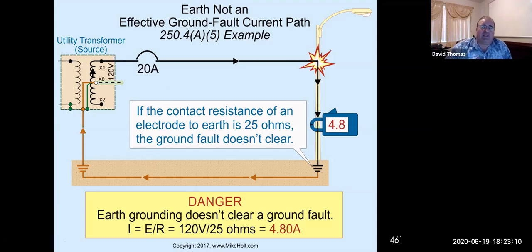And actually, this is the situation where that little girl got, well, not exactly like this one, but because the neutral was run to the light pole. Here you're not showing the neutral. But this is just to show you that if we use the earth instead of the neutral or the ground, it's not a good pathway. But that little girl that got killed in that Freeport car wash, this is basically what happened: they didn't run a ground wire, and so something shorted out, or ground faulted, and they were using the earth as a return path. They didn't install the ground properly, and that's why the breaker never tripped. And then she became the path of this current because she had less resistance in her body, especially being small. She was like 7 years old, so the current went through her and ended up killing her. Not enough to trip the breaker again. So we have to be really careful about knowing how to ground things properly.